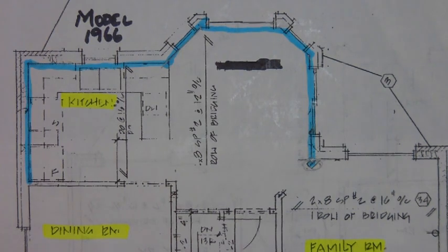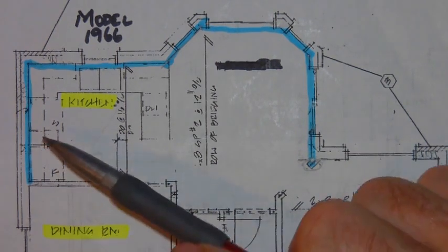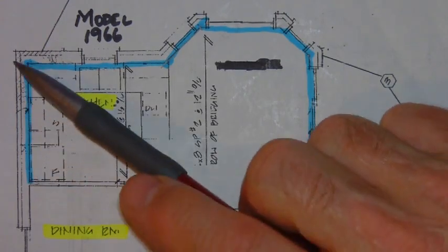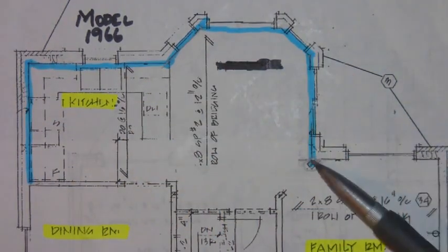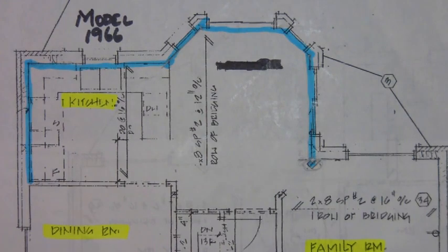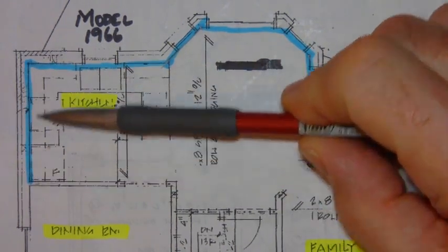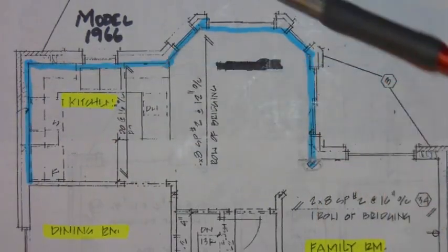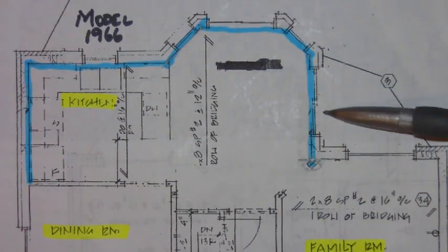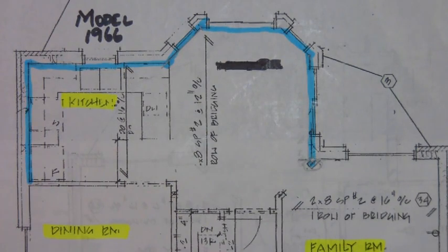When we measure a house, what we're actually looking for are the exposed surfaces where we will experience heat loss and heat gain. We'll need to find the area of walls, the area of any windows, and possibly, if there were any cold floors, you'd have to determine those areas. And on the second floor, we've got exposed ceiling, so you're going to have heat loss and heat gain through the ceiling. So we need to find all these different areas.